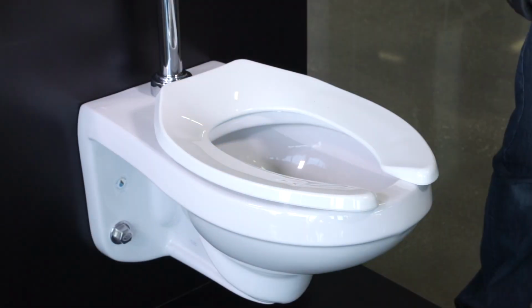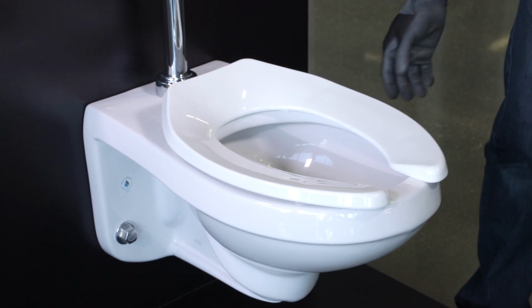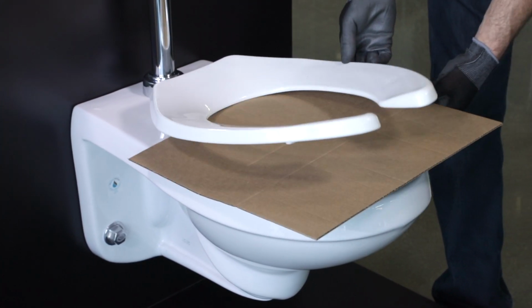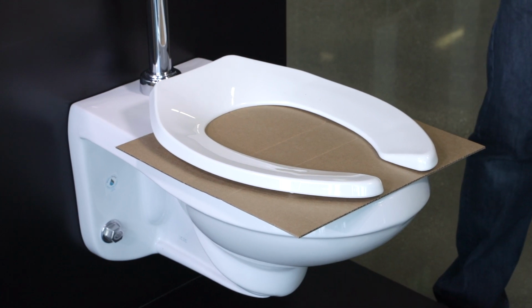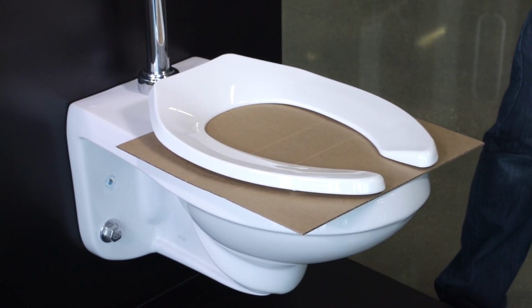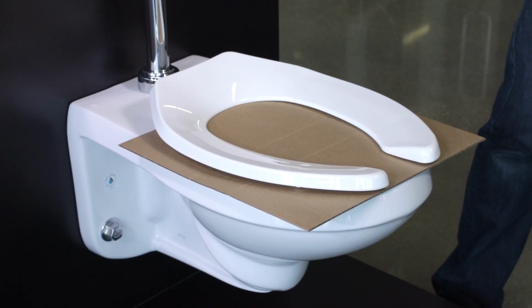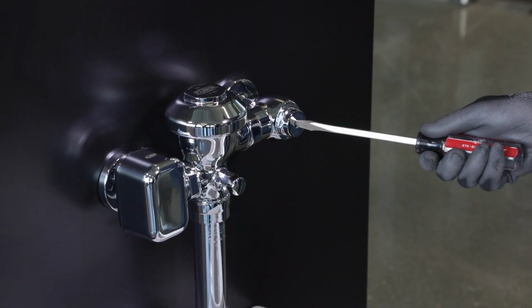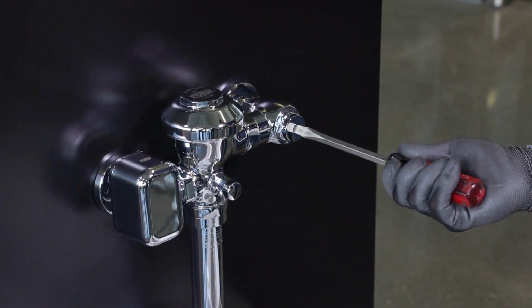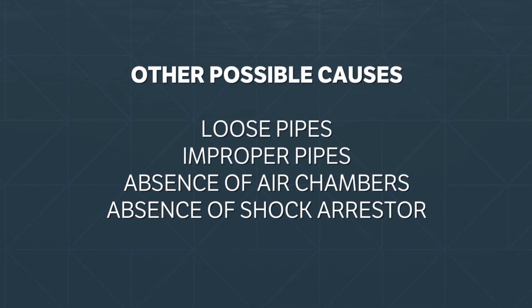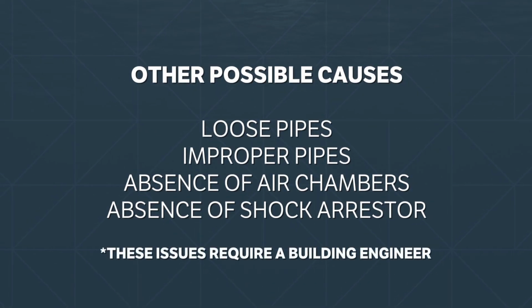Now, what if the flush valve isn't the problem? Check whether it's the fixture itself by placing a cover over the bowl opening, separating the valve noise from the bowl noise. If the bowl is the source, contact the manufacturer. High pressure within the piping can be controlled by the stop valve. Otherwise, you're looking at loose pipes, improper pipes, or the absence of air chambers or shock arrestors. These issues will all require a building engineer.